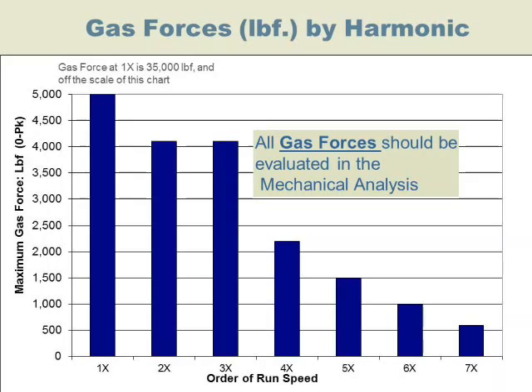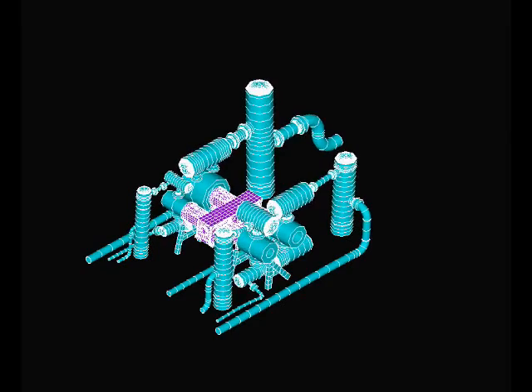The cylinder gas force is made up of different harmonics, meaning the vibration can occur at different orders of compressor run speed. This chart illustrates the amplitude of the gas forces at different frequencies or orders of run speed.